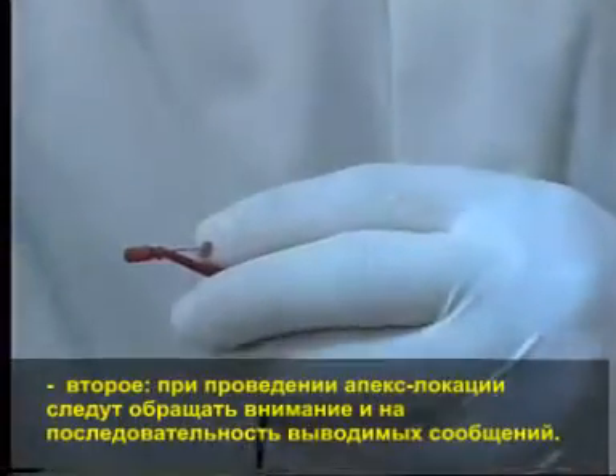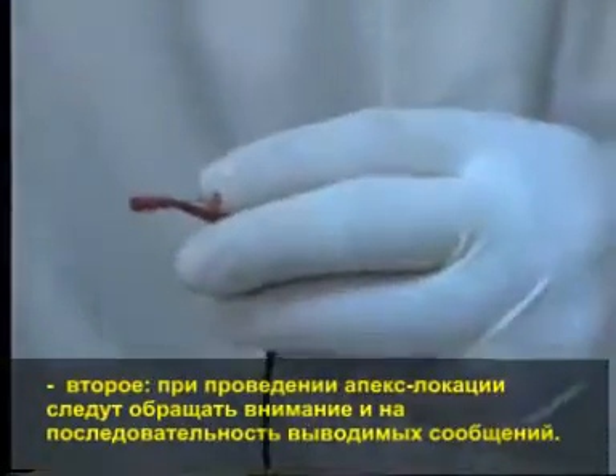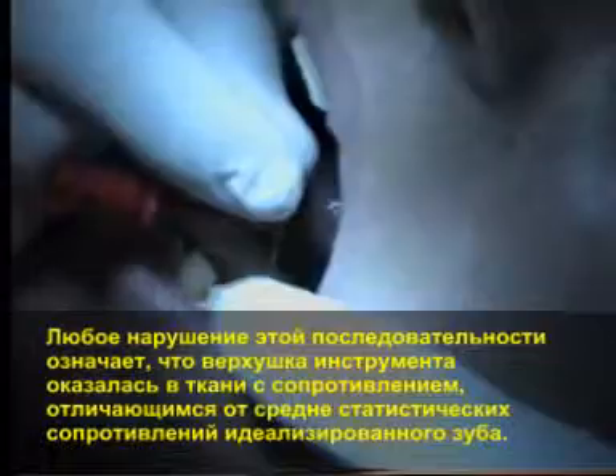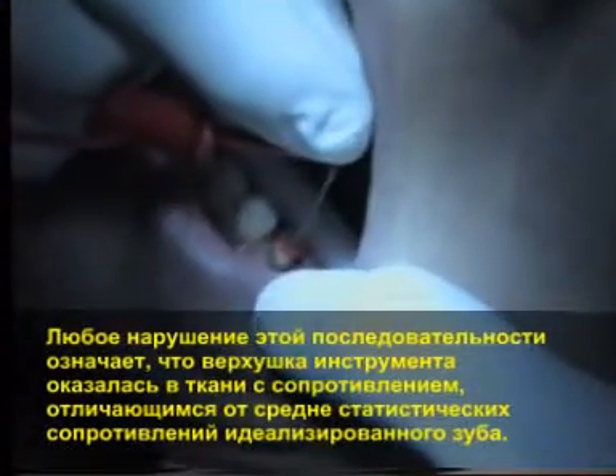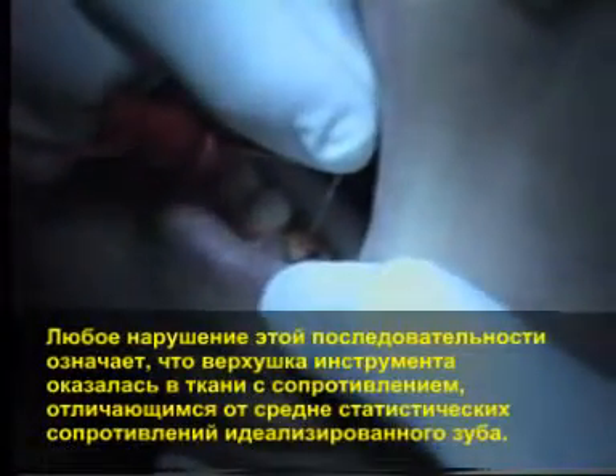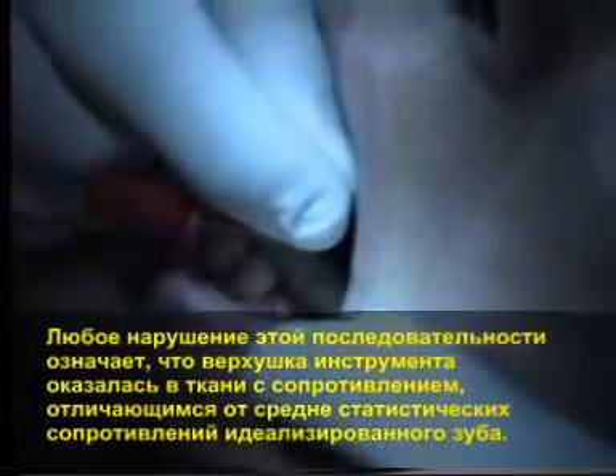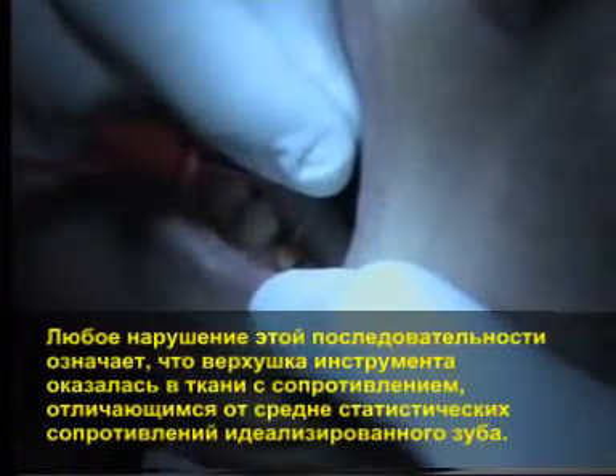2. When carrying out apex location, we should pay attention to the sequence of the oral and screen messages. If the sequence of these messages is different from the correct one, it means the instrument top has touched tissues with resistance different from the statistical ideal tooth resistance.